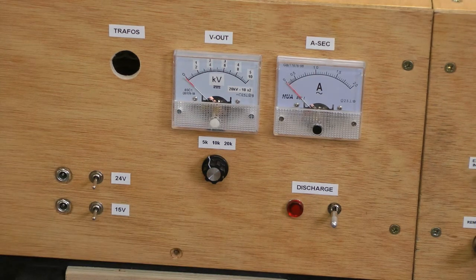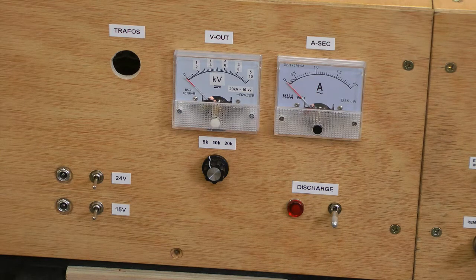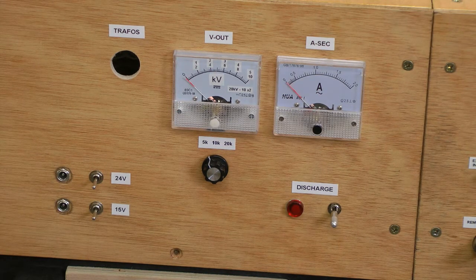The discharge unit is another subsystem inside. There you have vacuum relays switching the final HT output through a high power resistor. That's a sequence of 5 wire wound resistors, each 100 watts, making a total of 500 watts load. Each of those is a 4K7, so you end up with about 23 kilo ohms at 500 watts. And for discharging a capacitor, you could discharge a capacitor from 15 kilovolts using that.